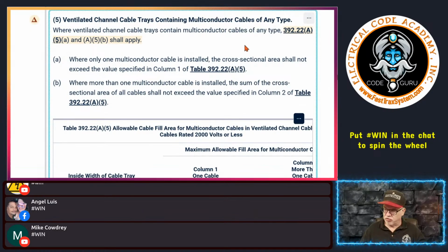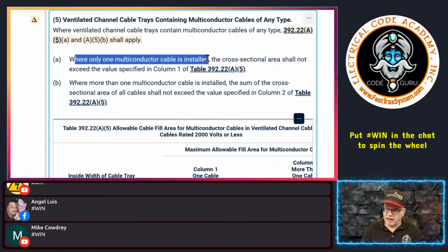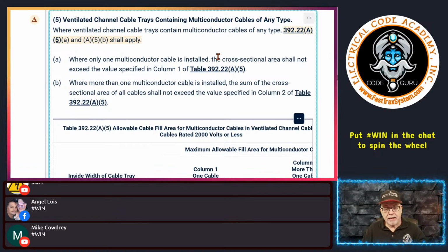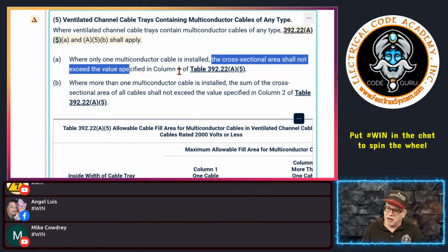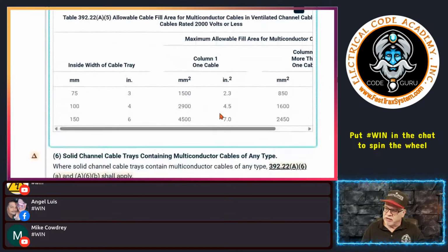It basically tells you to follow 392.22(A)(5)(a), which is right here, and (A)(5)(b), which is right here. So it says where only one multi-conductor cable is installed. Again, you'd be installing this ventilated channel tray for one multi-conductor cable, okay? Maybe it's a very important one cable, I don't know. But it tells us that the cross-sectional area shall not exceed the values of column 1 of the table right here. So these are your percentages.